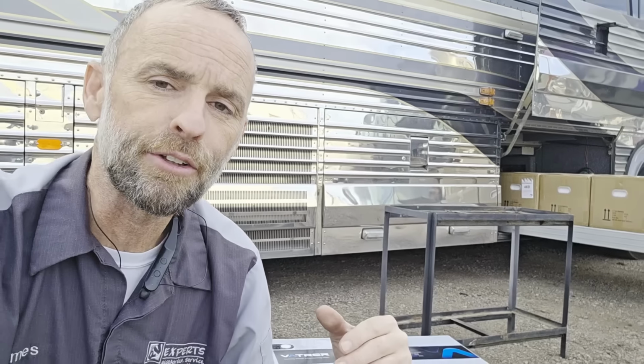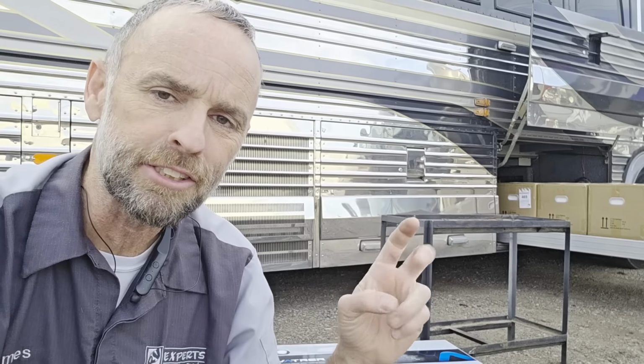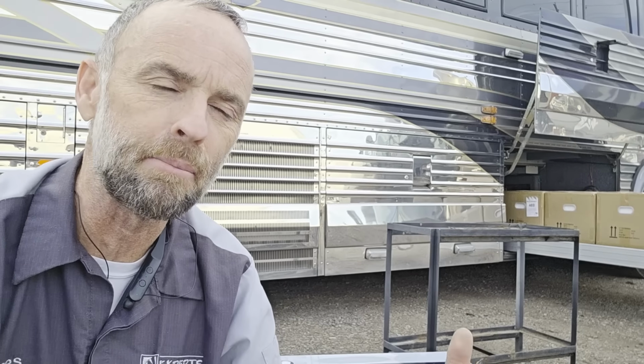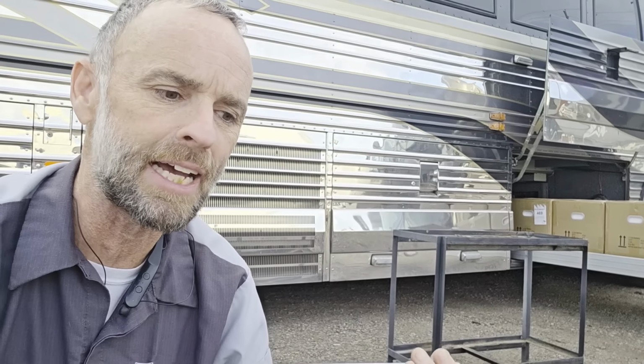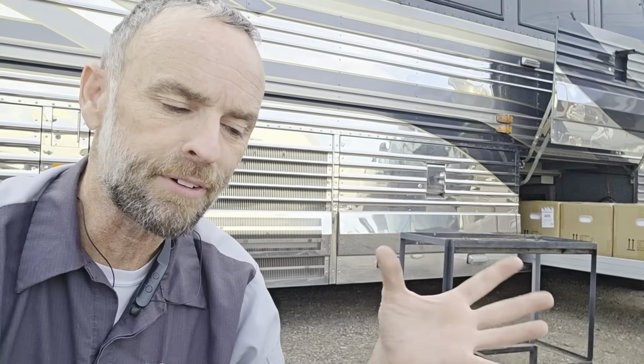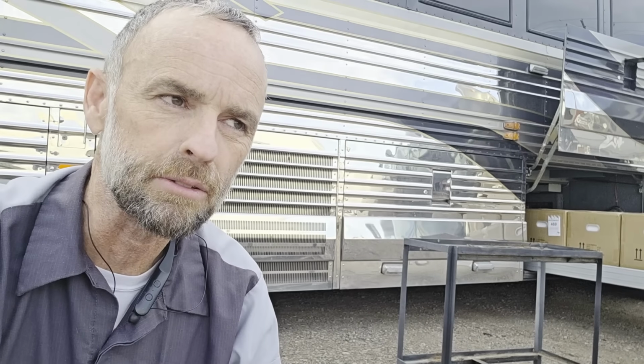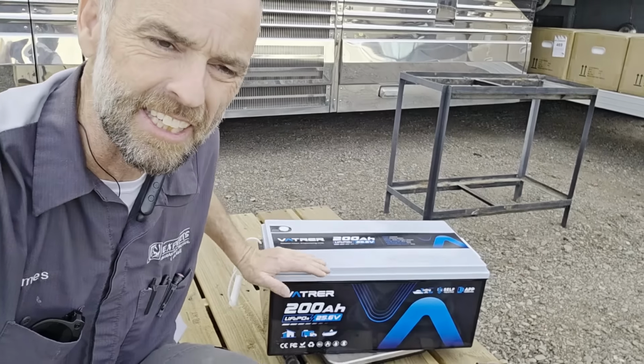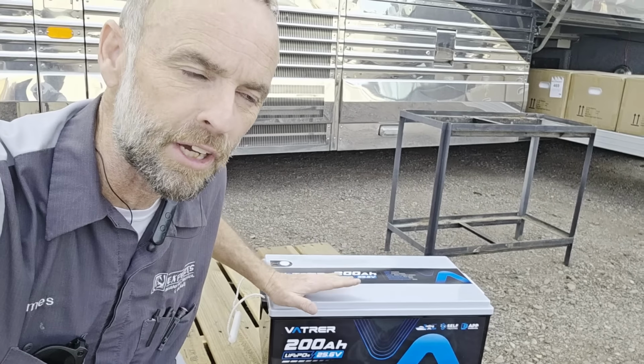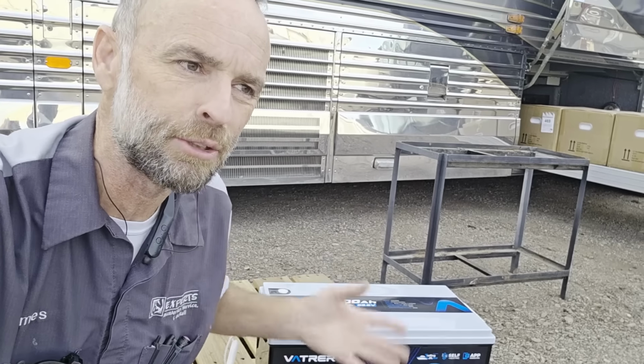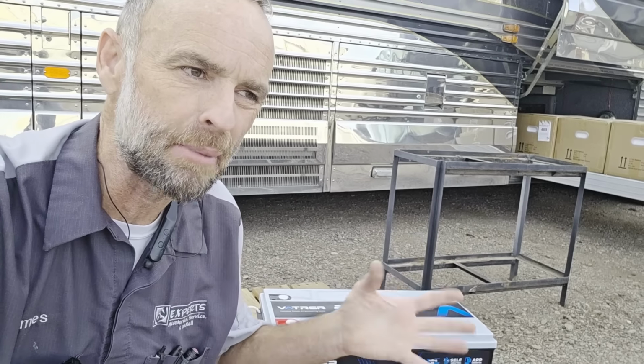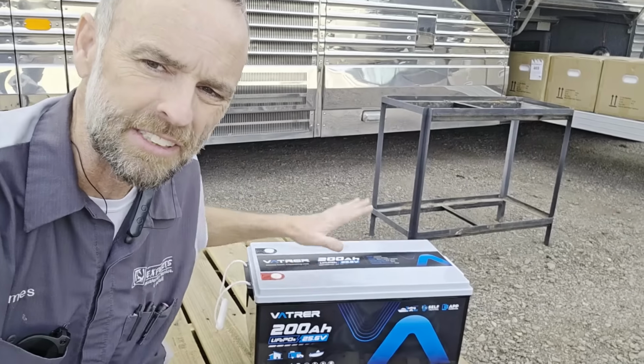The problem with AGMs, which are lead acid batteries, is that even though they're deep cycle, you should never routinely deplete them below 50% of reserve capacity. So out of 2,560 watt hours, you should never go below about 1,200 to 1,300 watt hours. With this battery, you get just over 5,100 watt hours usable, versus about 1,300 watt hours for the Renogy AGM, for basically the same footprint and size.